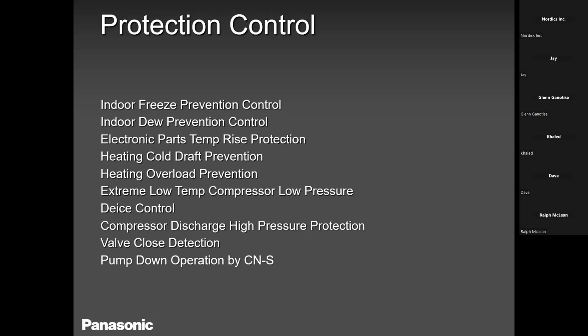So please try your best not to use dry mode for more than 2 hours. Dry mode is trying to maintain good humidity in the house. But keep in mind, as Jay said, our units are not dehumidifiers. They are strictly split units targeting set points on your temperature on your remote controller. It does not look for percentages and stuff like that. But keep in mind, guys, dry mode is only good for 2 hours. Don't leave it overnight, because if you leave it overnight, when the temperature drops, humidity drops, the coil gets pretty dry, pretty cool, and it will definitely shut off. And then when you wake up in the morning, you have an error. That's for indoor freeze. We do also have electronic parts temperature rise protection. Cold draft is the same as before. Cold draft prevention, we will talk about that as well, and the other stuff.